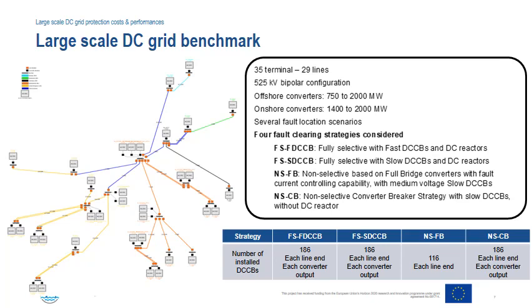Two fully selective strategies: the first using fast DC circuit breakers in series with the DC reactor, the second using slower and more cost-effective DC circuit breakers in series with the DC reactor. Two non-selective protection strategies are also considered. The first uses full bridge converters with fault current controlling capability, associated with medium voltage slow DC circuit breakers installed at each line end. The second one is a converter breaker strategy with slow DC circuit breakers without DC reactor.